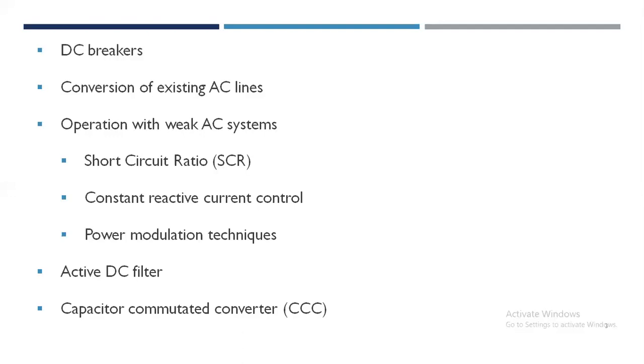The CCC can be combined with AC filters that have low reactive power ratings. These can be automatically tuned passive filters or active filters. The CCC technology was first applied in the Garabi BTB project for power exchange between Argentina and Brazil. This is rated at 1000 megawatt and SCR can be as low as 1.5. Another project incorporating CCC is a 200 megawatt station at Rapid City in the USA, commissioned in 2003. This is a BTB HVDC link that interconnects the eastern USA system with the western system. There is no synchronous interconnection between the two grids.